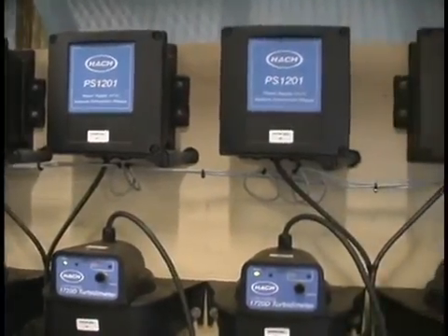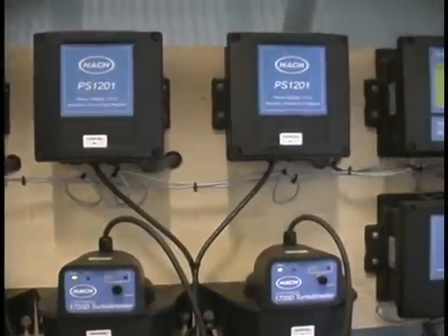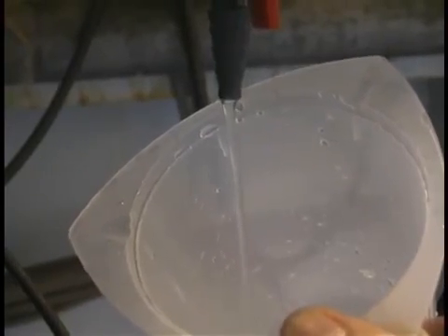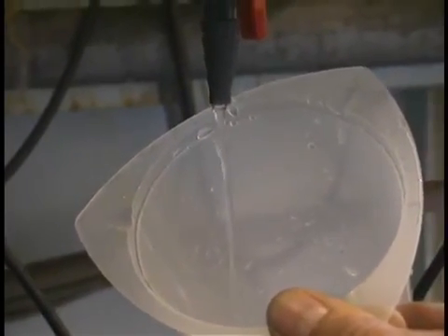Before the project started, we were getting raw water removed with the iron and manganese. The arsenic was coming down to about 35 parts. With this test project now, we're approximately running at about 7.5 to 8 parts.